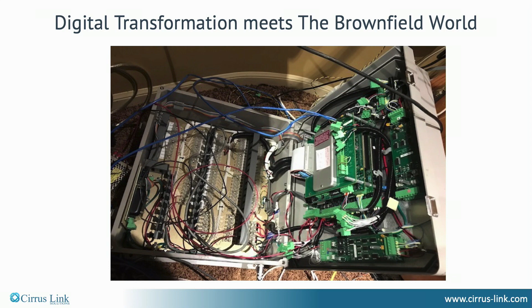So what if we could take that device and have the technology, let's say an edge device out at the edge of the network, to be able to get that Modbus holding register from 40,027 with a value of 126, and then be able to take that at the edge, using the Sparkplug spec, and transform it into an object?